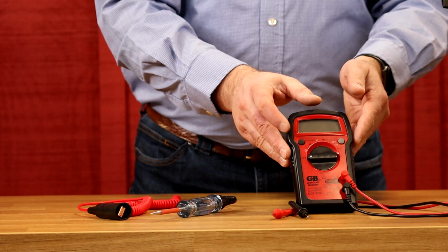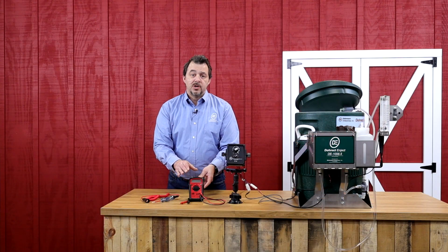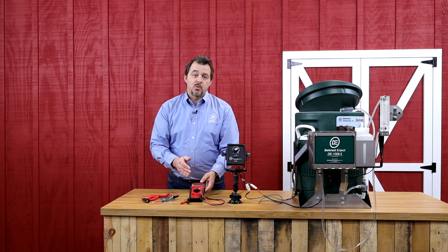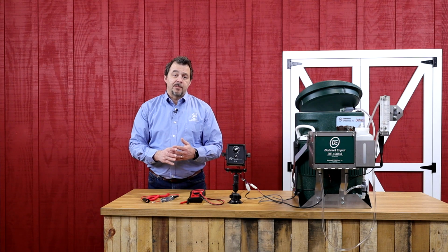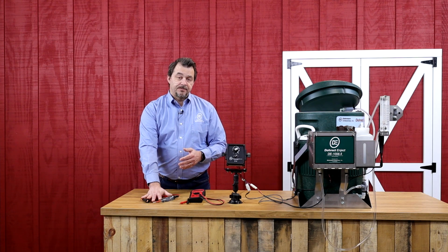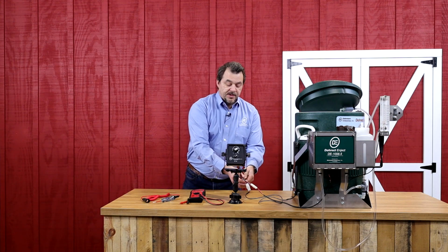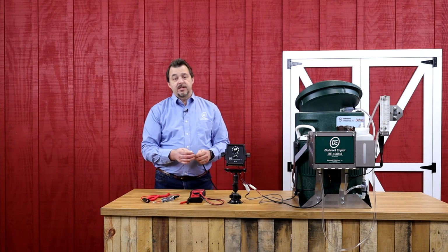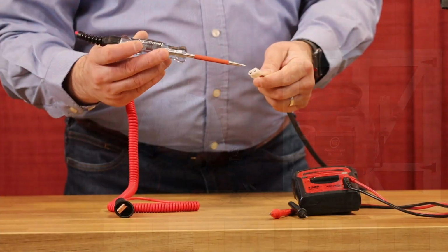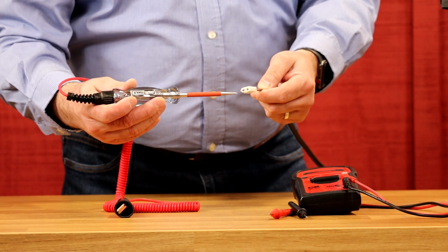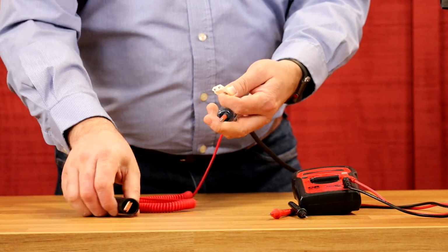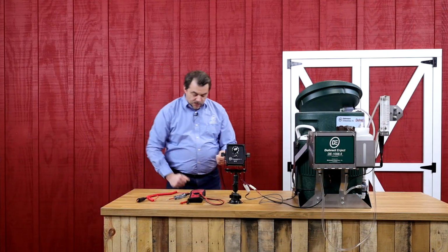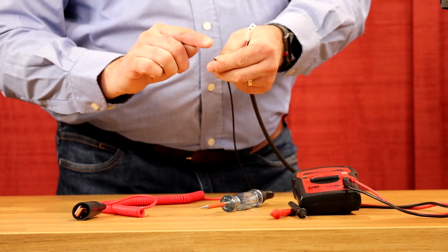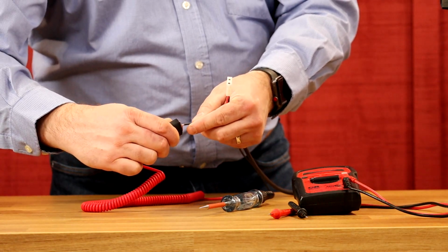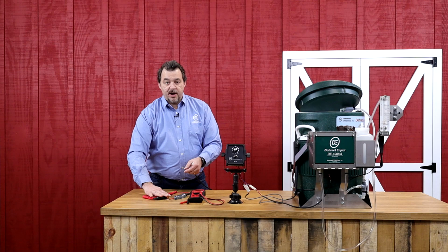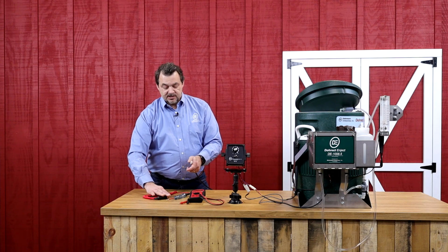It doesn't necessarily have to be a digital multimeter, but a multimeter is going to give us the ability to find out what the voltage is. We can also see whether it's wired correctly or not. So let me just show you an example of why we don't prefer the trouble light for verifying whether things are wired correctly. If we unplug the wire from the back of the controller and we've got the terminals here, the challenge is we can get inside these pins to see what we have for power, but we can't get into the ground. So a lot of times we'll end up going to ground someplace else. We'll end up using either a ground wire off of something else or say the frame of the tractor or chopper, and that's going to tell us that we have a good ground.